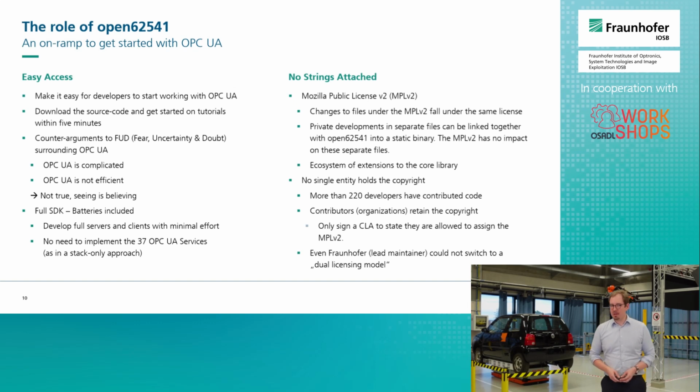So, and it's a full SDK that we provide. So you can develop full servers and clients with minimal effort. In other places, you get the stack, but you have to implement most of what the server provides, which are the services, the 37 core services. You have to implement them on your own. And here you only have to add information to the information model. But once the information model is done and potentially some callbacks to underlying devices, then you don't have to implement the OPC UA services on them. And very important, open62541 comes with no strings attached.